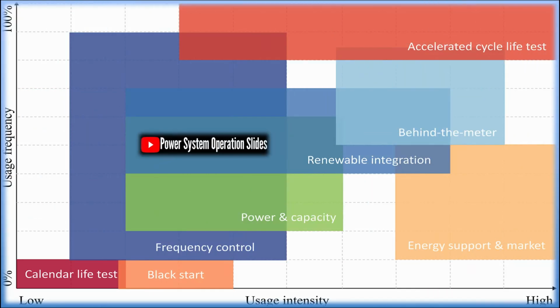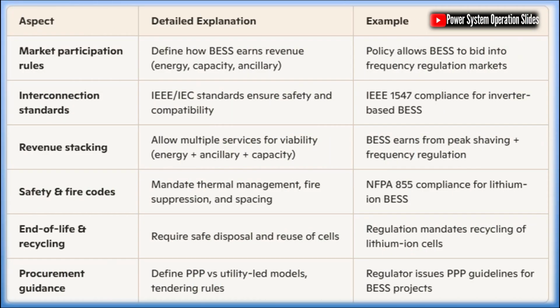that span technical, economic, and regulatory domains. BESS has evolved from an optional balancing resource to a core grid asset that enables high renewable penetration while maintaining system reliability. Correct siting, sizing, and voltage selection determine project success. Poor decisions in these areas can lead to underperformance, economic losses, and reduced grid reliability. Degradation modeling is particularly critical, as poor assumptions can cause both financial and operational failure, as demonstrated by the California experience.